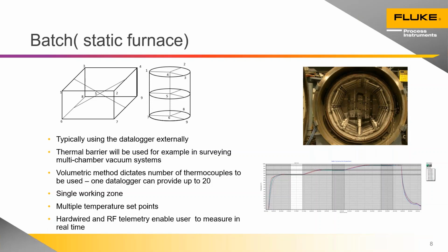Thermocouples used are generally mineral insulated. Most surveys are conducted with thermocouples with no heat sinks on the tip. And the wire frame diagrams here show some typical thermocouple layouts for a rectangular working volume and a cylindrical one. So for volumes in excess of 1/10 of a meter cubed, sensors are placed to measure the working volume. So we have 4 at the top corners, 4 at the bottom corners, and 1 in the center.